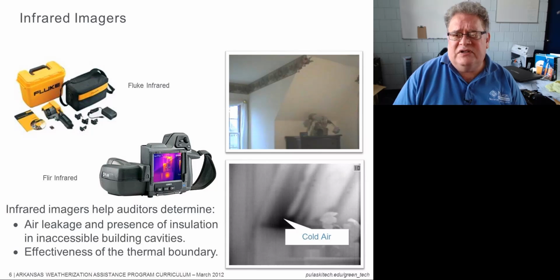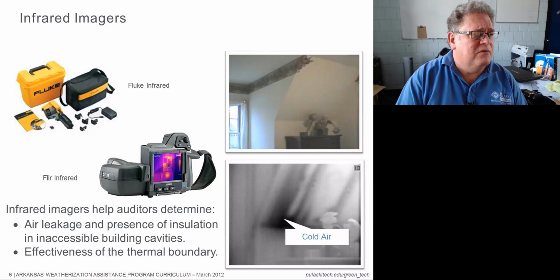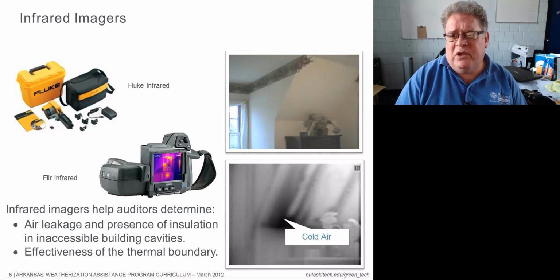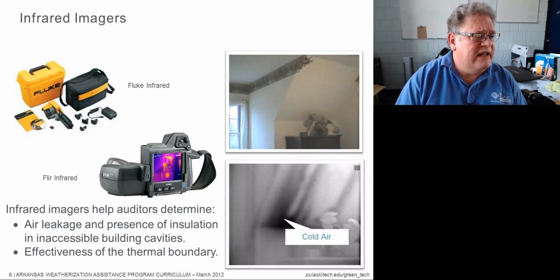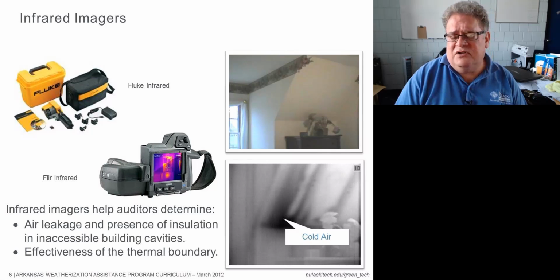But infrared allows you to see things that you normally would not be able to see, because it's letting us see in a part of the light spectrum that our vision can't detect. So here on this right-hand picture, for instance, in the top one, when we look at just a regular visible light picture, we are seeing the inside of a bedroom. Looks like a dormer, that's popped out there on the left with a dresser underneath it. But when we look at it in conjunction with the blower door under infrared, what we are seeing is streaking caused by the temperature change of the sheetrock, the surface of the sheetrock, and that's caused by air either moving over it or, in this case, I would suspect behind it.